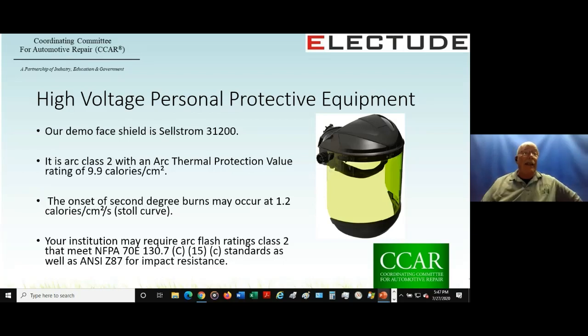Or you might realize that the onset of a 2nd degree burn may occur at 1.2 calories per square centimeter. That's the Stoll curve. That goes back to the Navy in the 40s. But the best description I've ever heard for understanding is that 1 calorie per square centimeter can be approximated to holding your finger over the tip of a lit cigarette lighter over that flame for 1 second. Now, most institutions that require arc flash ratings will have you meet arc flash 2. And in the case of this face shield, the Z87 is for impact resistance only.